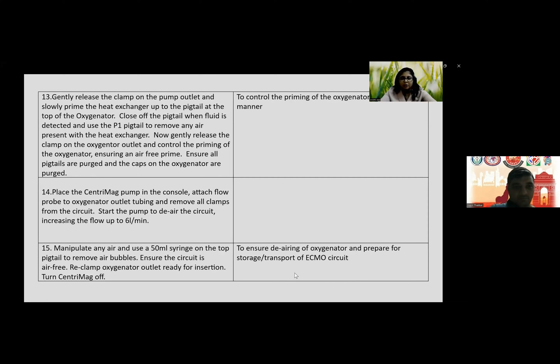This is to ensure the de-airing of the oxygenator and prepare for the storage or transport of the ECMO circuit. Then you clamp both the tubes between the reservoir bag and sterile priming tray. Carefully remove the gauze tape securing the lid. Remove the lid and allow the sterile tubing to be removed by a person in the sterile field. Ensure that the reservoir bag is held securely during this procedure.